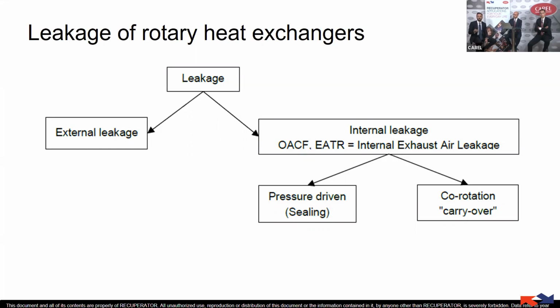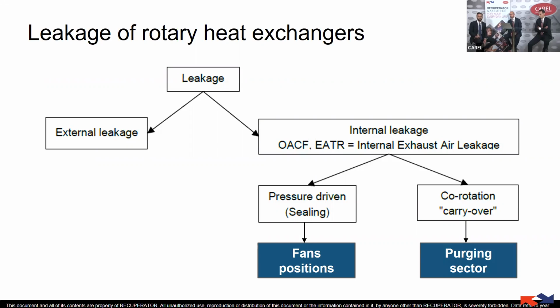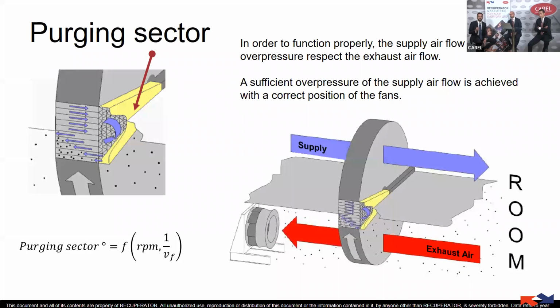The internal leakage can be influenced by the pressure difference, the differential pressure that we've seen before. If you remember, with the plates, this is the difference in pressure between the two airflows. There is also a new one, the co-rotation, also called carryover. The first one is influenced by the fan position, so we can control it with the fan position, and the other one can be controlled with the purging sector. Let's now focus a little more on the last, carryover and the purging sector. The carryover is the phenomenon of transferring particles of the exhaust air to the supply air.